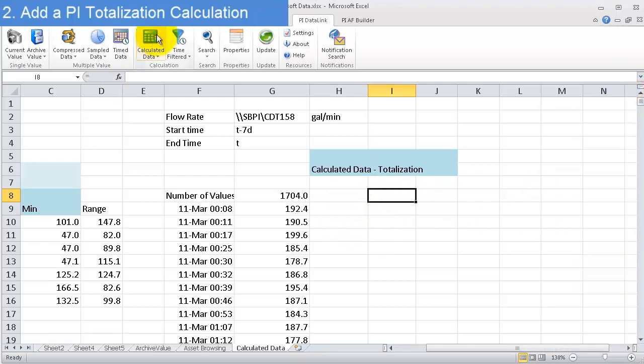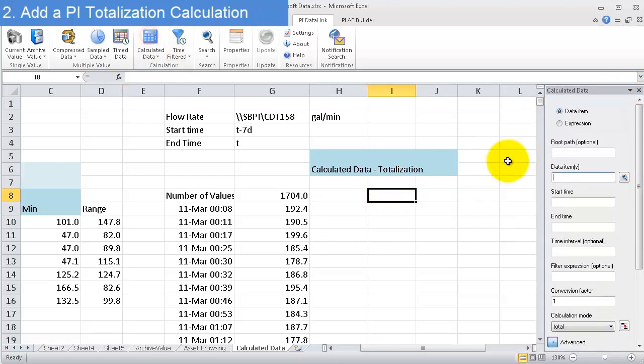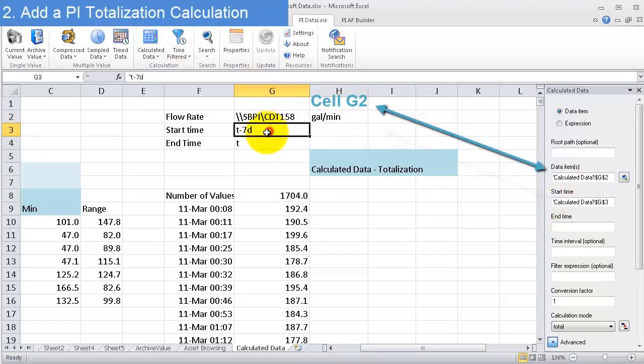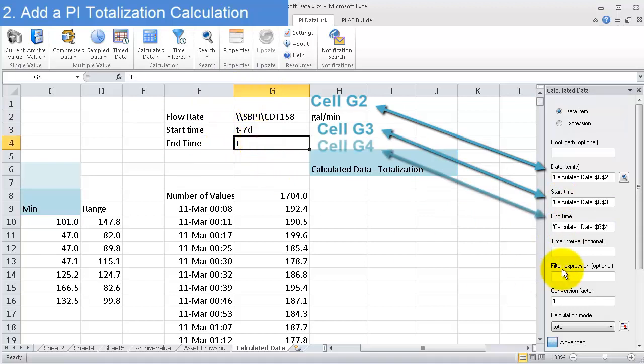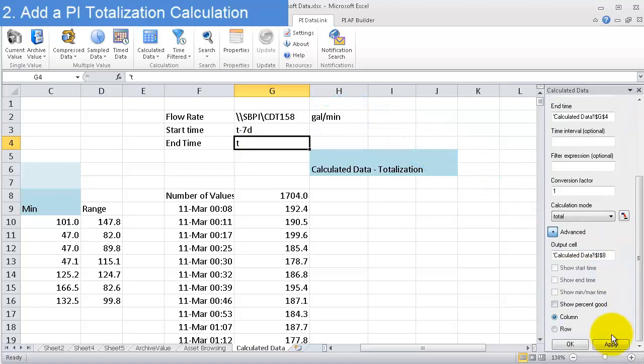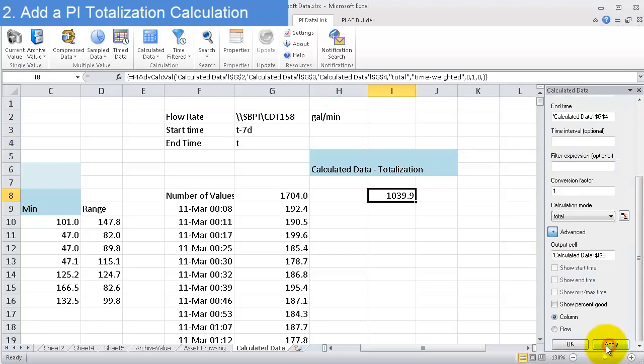I'm just going to say calculated data, data item. Well, it's my PI tag right here. And the start time is clicking on G3, that's the start time. The end time is clicking on G4. Time interval, you don't need to use that right now. I'm interested in the number of gallons I had over the whole week. We'll see that in just a moment. And then I click apply and I get a value.